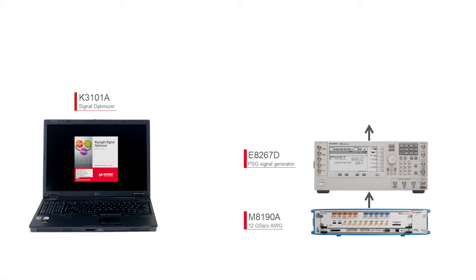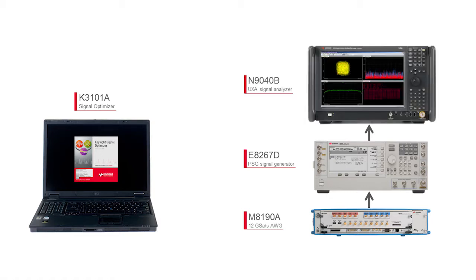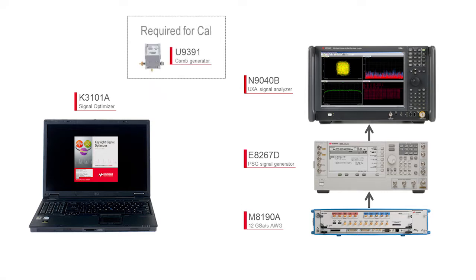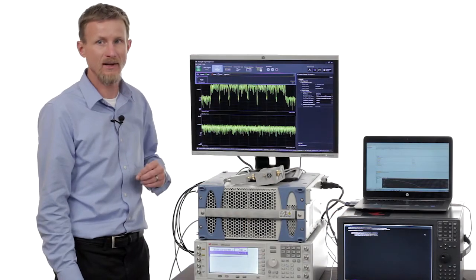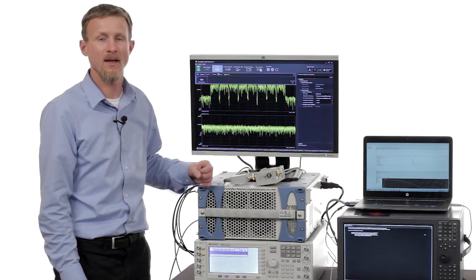This is connected to a signal analyzer, the UXA, which has 1 gigahertz of bandwidth. We'll use that to digitize the signal and then make measurements. Also, we have a comb generator — this is what enables us to do the calibration. This generates an extremely wide bandwidth comb signal, all the way up to 67 gigahertz. We know the exact amplitude and phase of each of those CW signals coming out of the comb generator, and that's what enables us to do the initial calibration on the receive part of the test setup. Then we'll do a calibration of the source side as a second step.